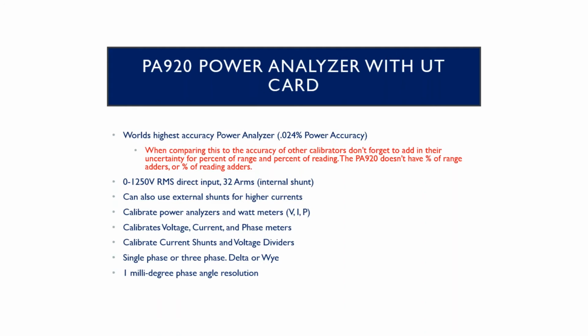So this PA920 is used typically for calibrating power analyzers and watt meters. But depending on what you're calibrating, it's also good for calibrating voltage meters, current meters, phase meters, and you may want to use it for calibrating current shunts and voltage dividers. If you've got a source with a precise known current, you plug your shunt into our device, we will read the response, and we can see the error caused by your shunt or your voltage divider. So it's really good for quite a few different instruments in your lab.